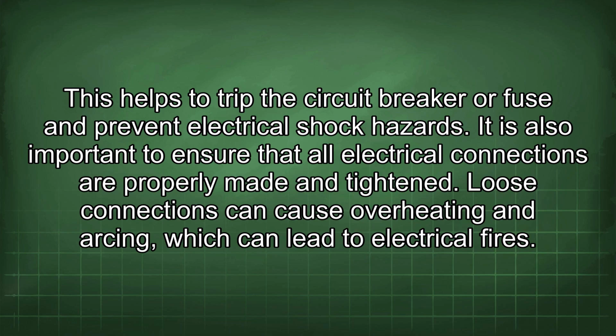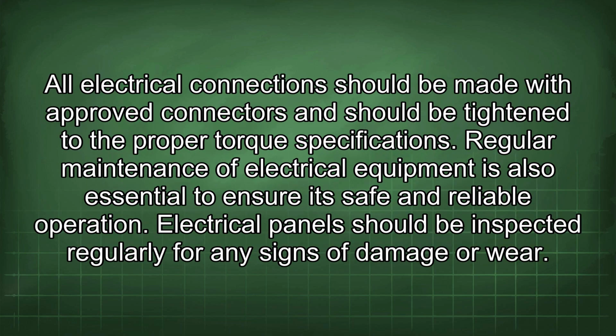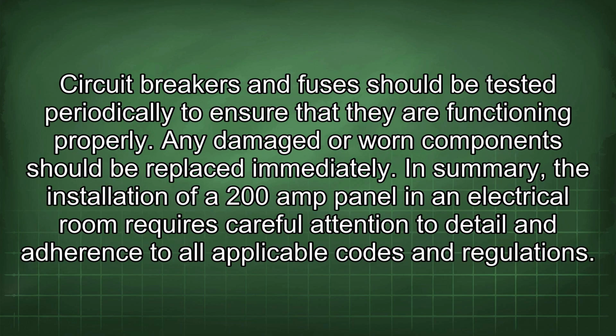It is also important to ensure that all electrical connections are properly made and tightened. Loose connections can cause overheating and arcing, which can lead to electrical fires. All electrical connections should be made with approved connectors and should be tightened to the proper torque specifications. Regular maintenance of electrical equipment is also essential to ensure its safe and reliable operation. Electrical panels should be inspected regularly for any signs of damage or wear. Circuit breakers and fuses should be tested periodically to ensure that they are functioning properly. Any damaged or worn component should be replaced immediately.